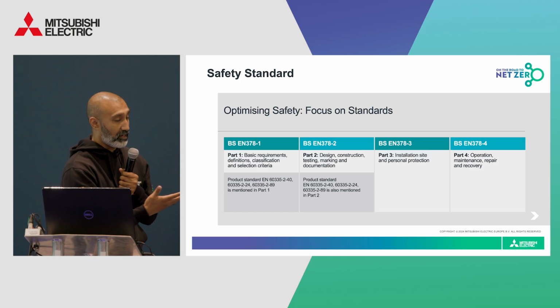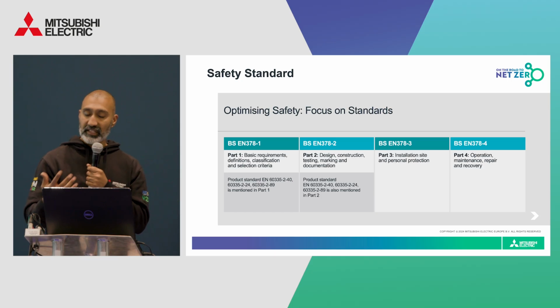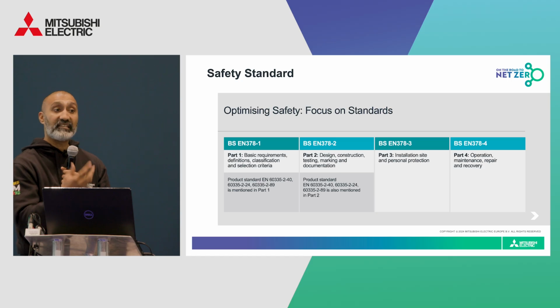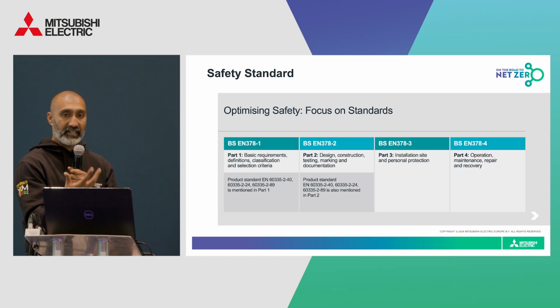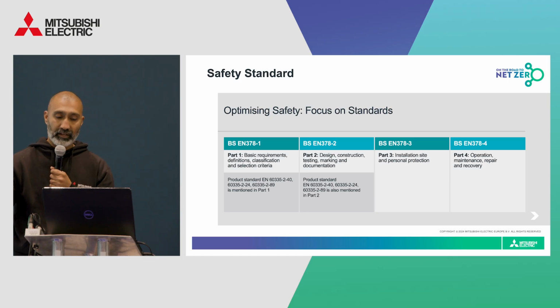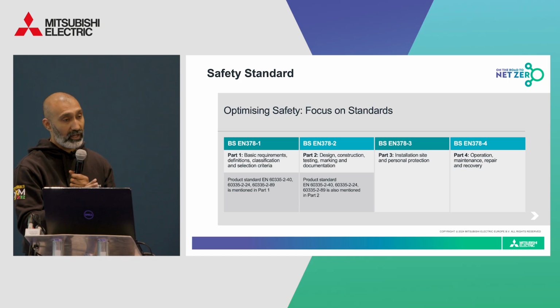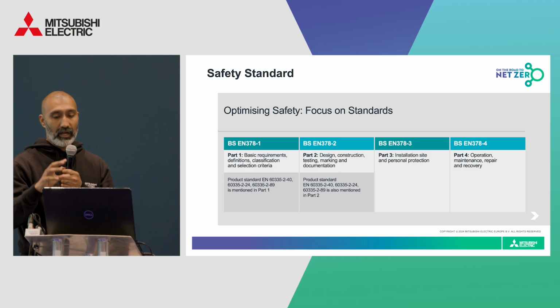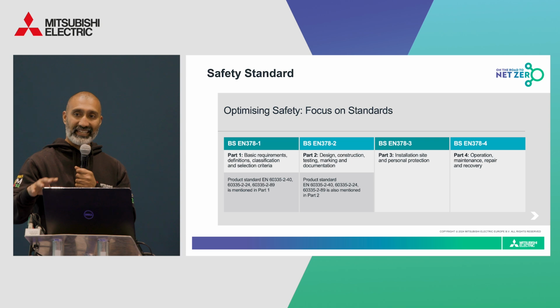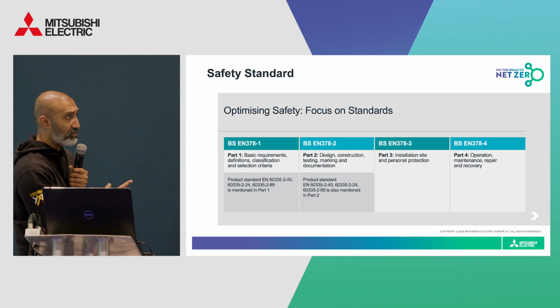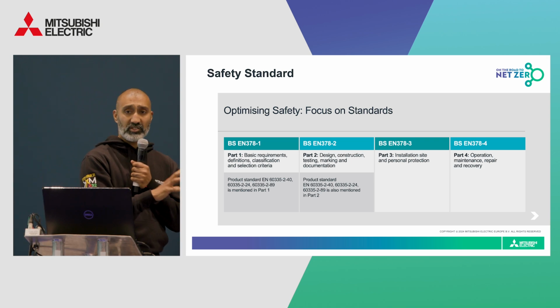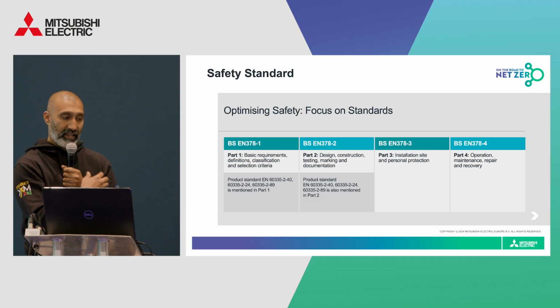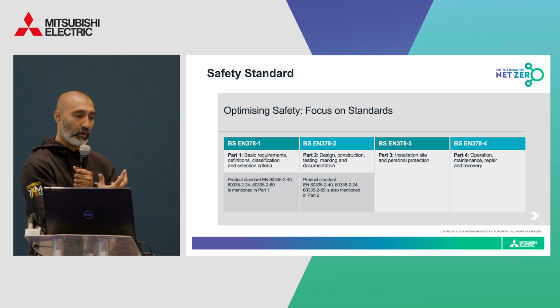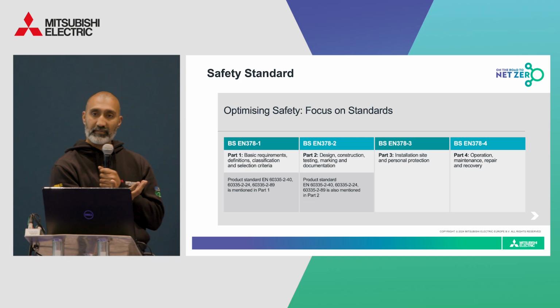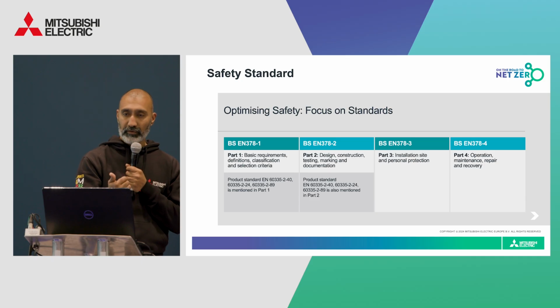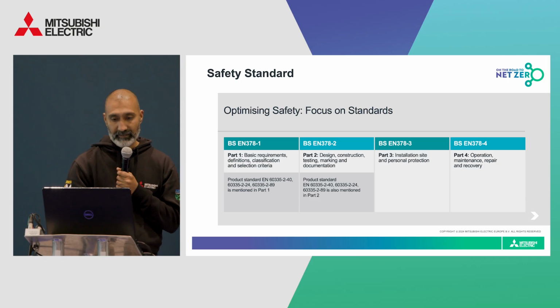So part 2, as an example, focuses on manufacturers, installers, and maintenance personnel. And this division divides the responsibility across different stakeholders to make sure that all relevant risk assessment has been carried out across the life cycle of that equipment in that building. And here as well, with EN 378, a consultation recently closed, and the consultation was looking for feedback on the proposed updates to try and better reflect modern refrigerants and modern technologies.